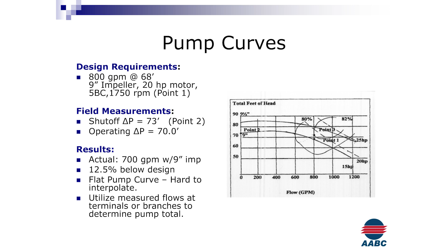In this case, I know exactly what's going on because I have a very steep curve. So I can come out here with the same pressure and know I'm doing 200, or I can look here and know I'm doing 600. I can look at that quickly and there's no guessing. I can look at the pressures, plot them, and the question of what GPM I'm actually on becomes very narrow. Then we can start to look at whether the impeller is wrong, whether the motor isn't sized correctly, and what else is going on. But at least I'm able to tell exactly what GPM we're doing at a given point.